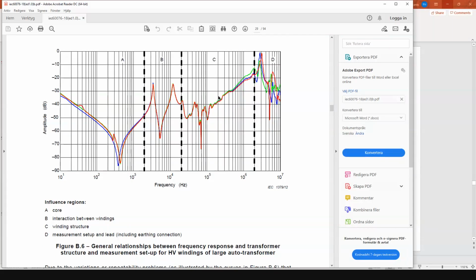Right. Another question that we are having is, what is the minimum rating of a transformer that SFRA is applicable? I would not say that there is a minimal rating. You can apply SFRA to any transformer, basically. If you can use a test box, like this field verification box, to measure, then you can measure on small transformers, you can measure on big transformers. So I would not see any rating limitations here.